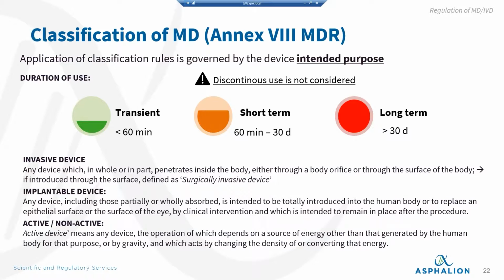Then you've got to consider the invasiveness of your device. Devices that penetrate inside the body through a body orifice or through the surface of the body are considered invasive. If they are introduced through the surface of the body, they are considered surgically invasive devices because they require an intervention to get within the body.